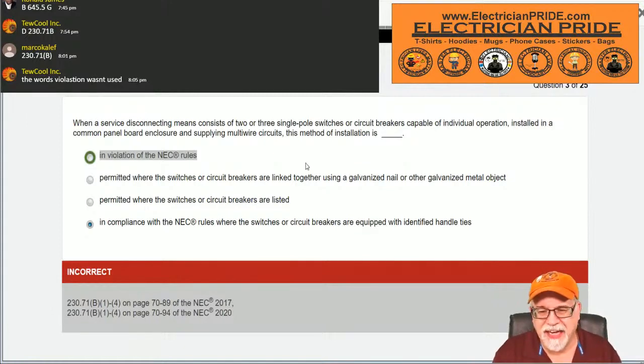It doesn't have to use the word violation. It would be a violation of the code because the code requires you to have a main disconnect. You can't use a 6-disconnect rule anymore. So it's not going to say it's a violation, but if you can't meet options 1 through 4, then by its own right, it would be a violation.